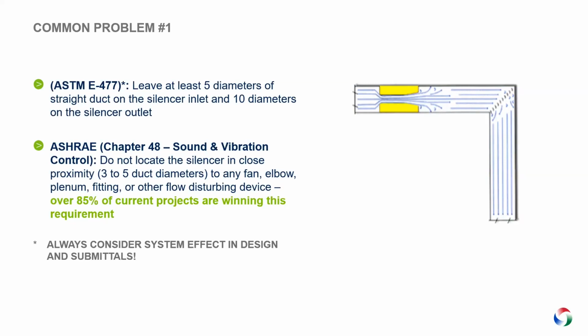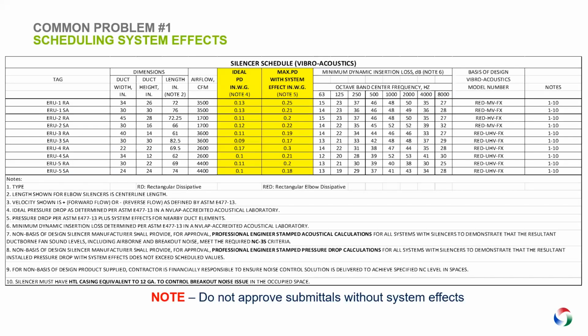So which means if we are testing a 5-footer silencer, we are having 20 to 25 feet of straight duct, which we normally do not see on the mechanical drawings. That's why it's very important to look into the system effect pressure drop.